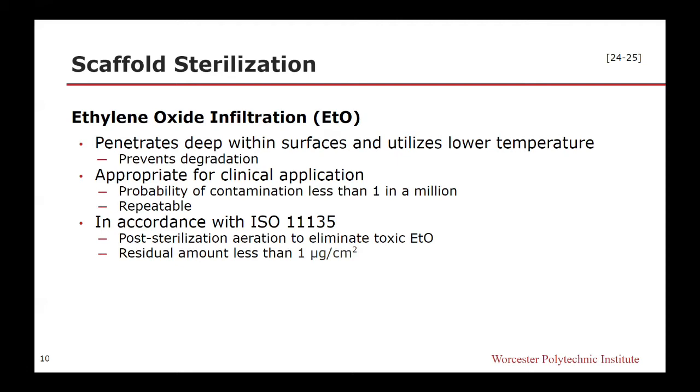After exposing the scaffolds to ethylene oxide, they will be aerated with warm air at atmospheric pressure for 2 days to eliminate any toxic ethylene oxide. Studies have shown following this procedure minimizes the residual amount of ethylene oxide to less than 1 microgram per centimeter squared.